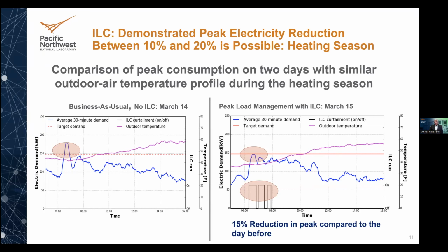We demonstrated that ILC can be used on real buildings during heating, cooling, as well as swing seasons to reduce peak consumptions between 10 and 20%. In this slide, I'm showing a comparison of peak consumption on 2 consecutive days, March 14th on the left and March 15th on the right. The graph on the left shows results when we are not managing the peak. The graph on the right is when we are managing the peak on the very next day.